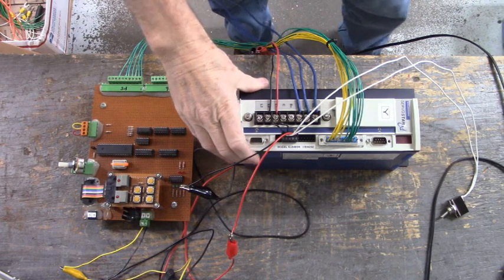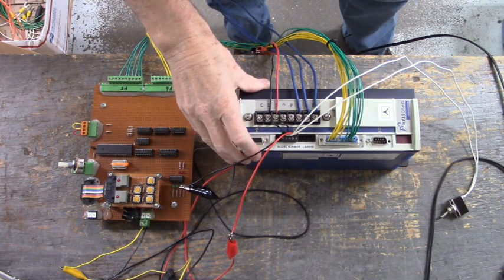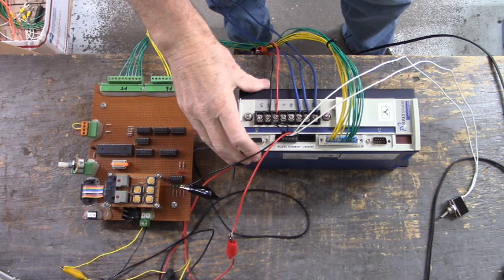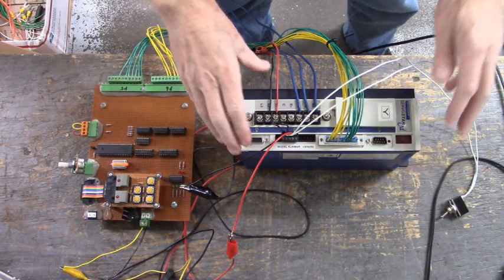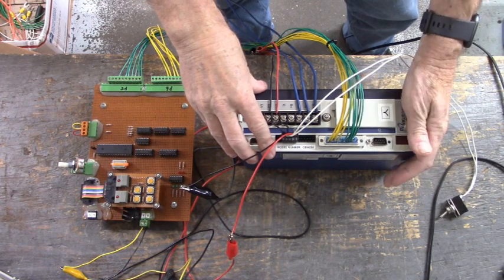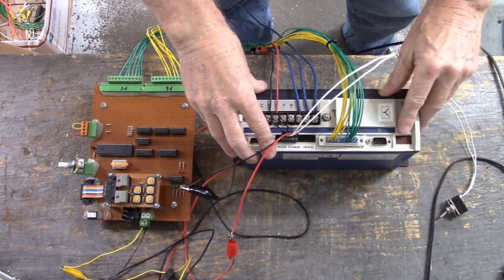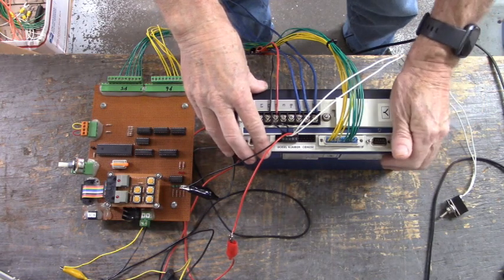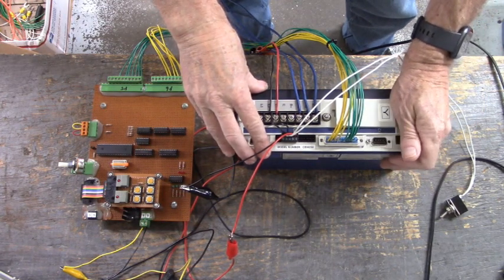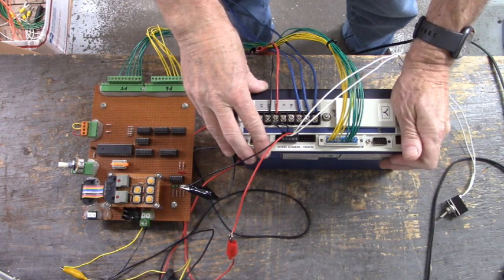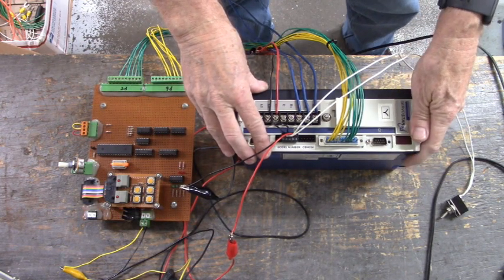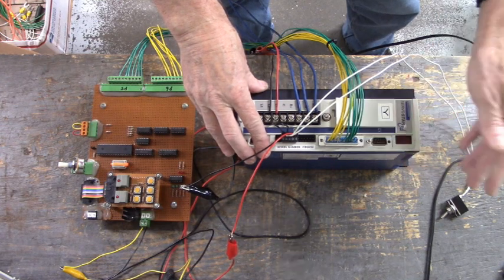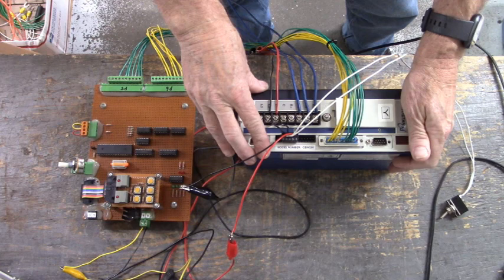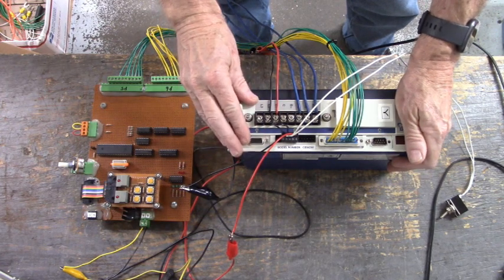But today, we're going to test this Kollmorgen ServoStarCD, model number CE6250. Its problem was that every now and then, it would not power up. The 7-segment display would be blank. And I've recapped it. I'll show you the one bad cap that was preventing the power supply from starting up every now and then. It was a 100 microfarad 16 volt surface mount capacitor. But now, with new capacitors, it's powering up and we want to test this drive.